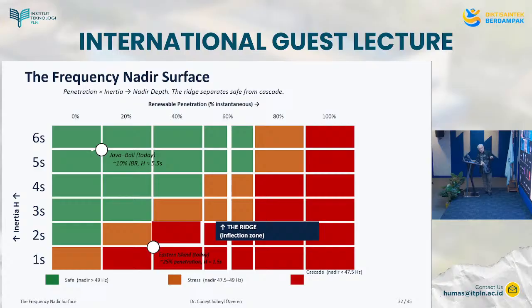So this is a graph which shows you the inertia constant in the y-axis, and on the x-axis you have the renewable penetration, right? So you can see that even with low renewable penetration, Eastern Islands are in the red zone. It's because the percentage of the inverter-based resource is high, so it's a low inertia system. So they are continuously kind of between orange and red zone. Whereas as the renewable penetration increases to about 60%, Java Bali will still be in the safe zone, right? And that's where you have the 60% coal reduction anyway.